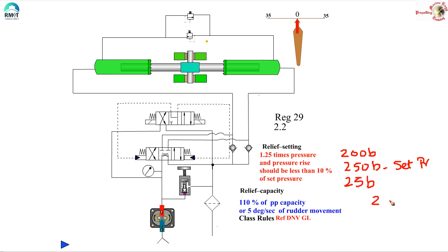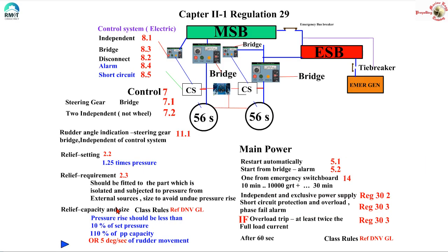Why does this accumulation of pressure happen? When the relief valve lifts up, the spring gets compressed and as it compresses the relief valve setting also increases — that is what we call accumulation of pressure. Regulation 29.2.3 states that the relief valve should be fitted to that part of the hydraulic circuit which is isolated and subjected to pressure from external sources — pressure rise — and the size should be such that it avoids undue pressure rise.